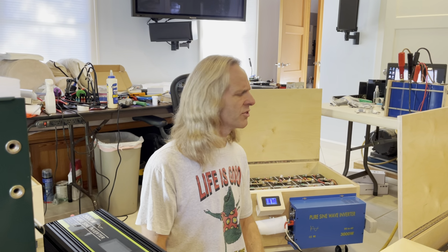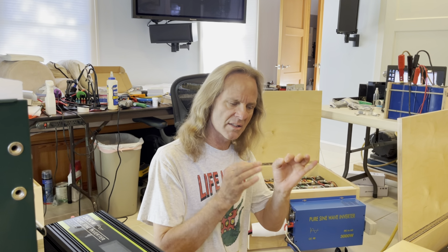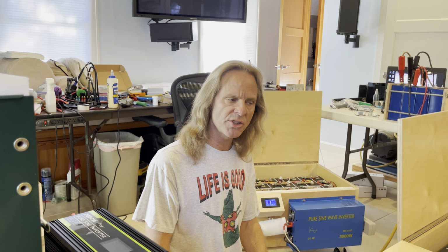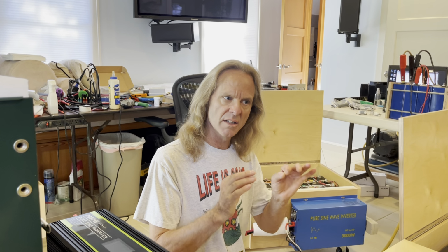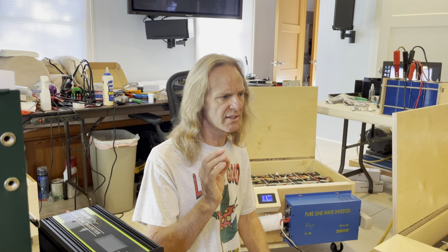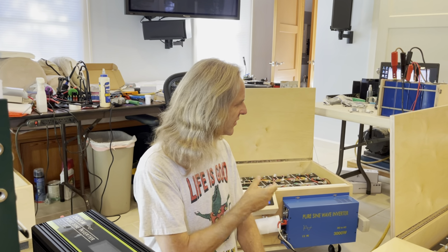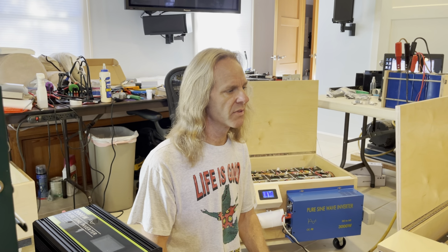Checked it on top of the bus bars, 100 millivolts different. Turned the charger off, checked on top of the bus bars, the same. Only while charging and measuring the bus bar was it a problem. There was evidence that something was wrong yesterday. Cell number 11 started to act differently, right along with cell number 12, at some point.